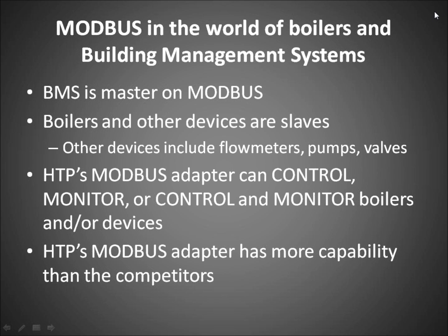Can one of the engineers comment on that? We evaluated some of the competitors' ModBus capabilities, and there were some things that we pointed out in the meeting yesterday that we felt were prudent. What are those? The big thing is that the competition's ModBus adapter doesn't have any visibility of data from cascaded boilers. So on the competition, if you want data from cascaded boilers, you have to have a ModBus adapter on each boiler. Whereas on our product, one ModBus adapter will give you, on cascaded boilers, a bit of information back from each of the follower boilers, as well as full information from the master boiler. Okay. Thanks, Steve.